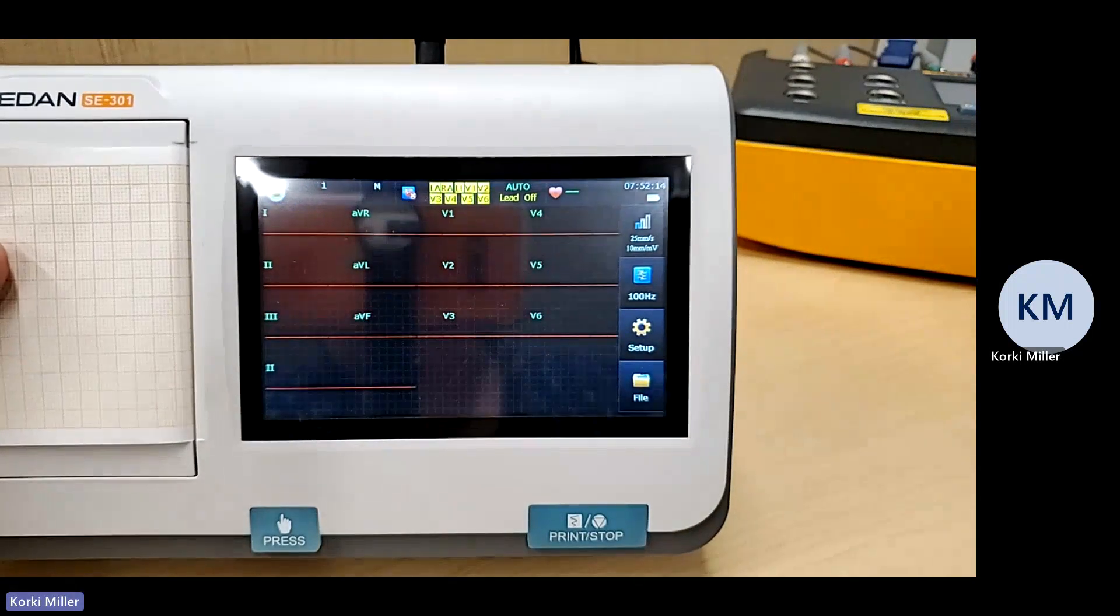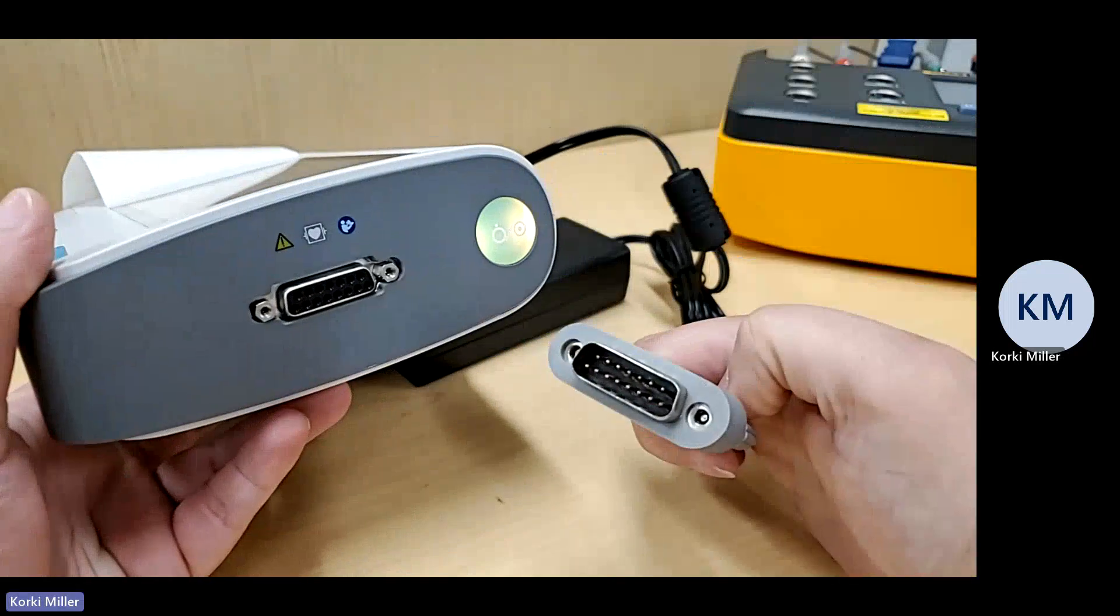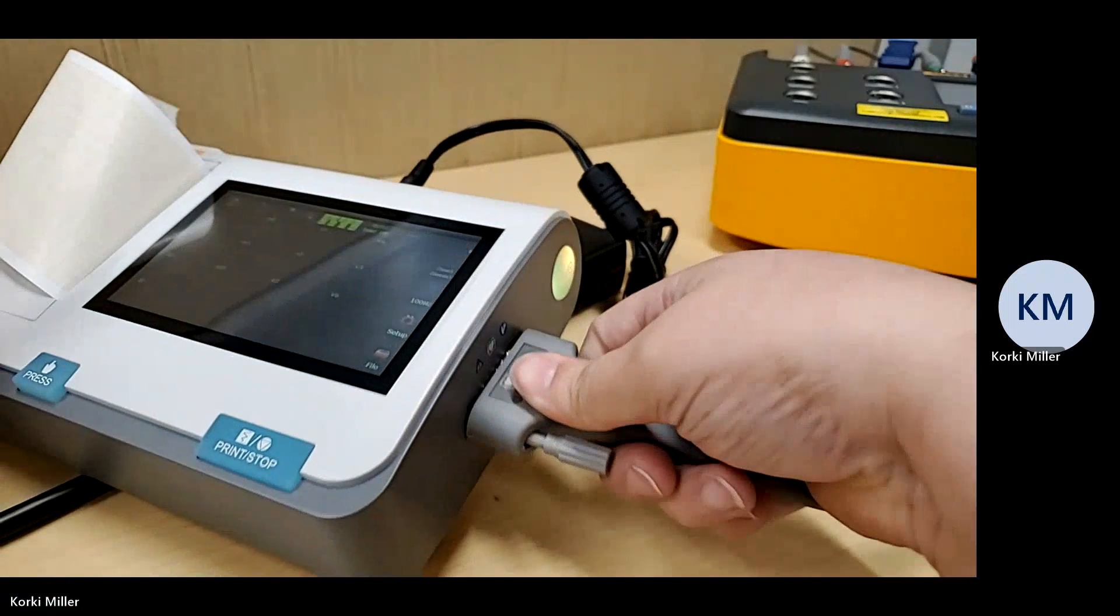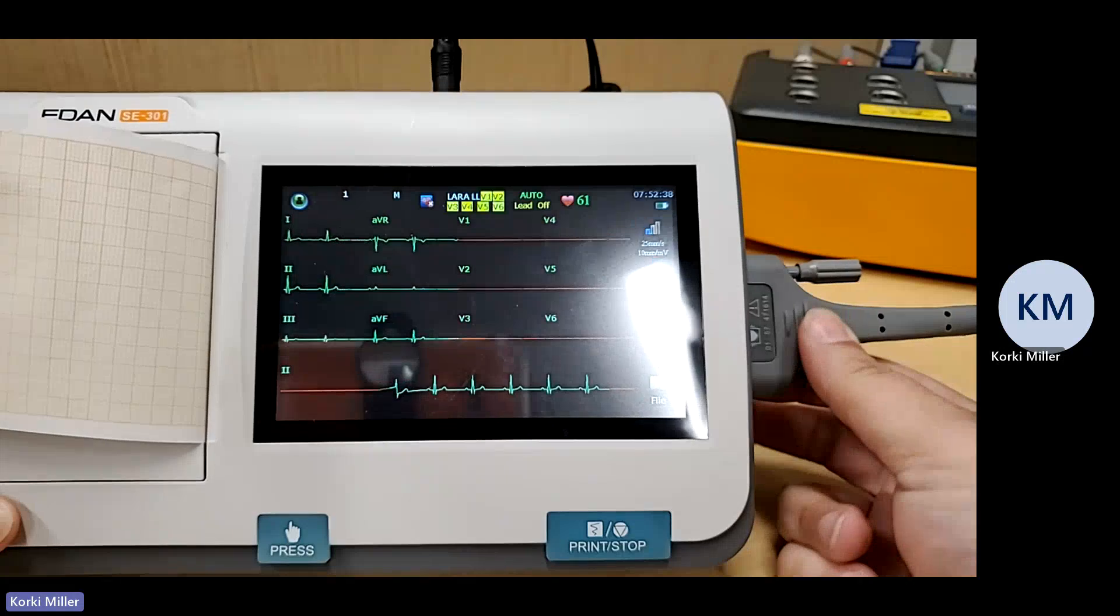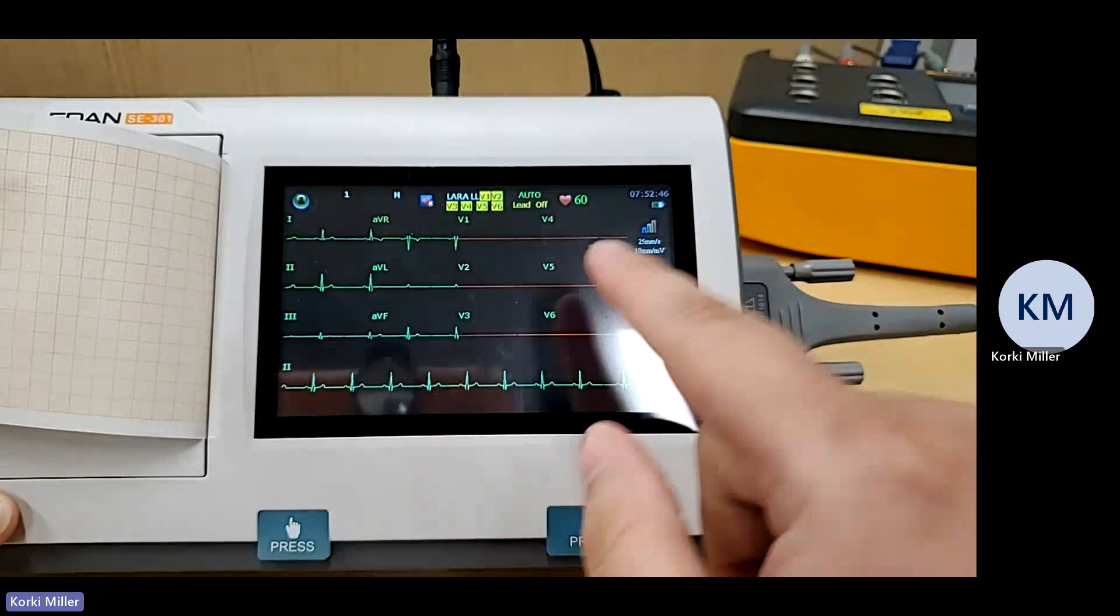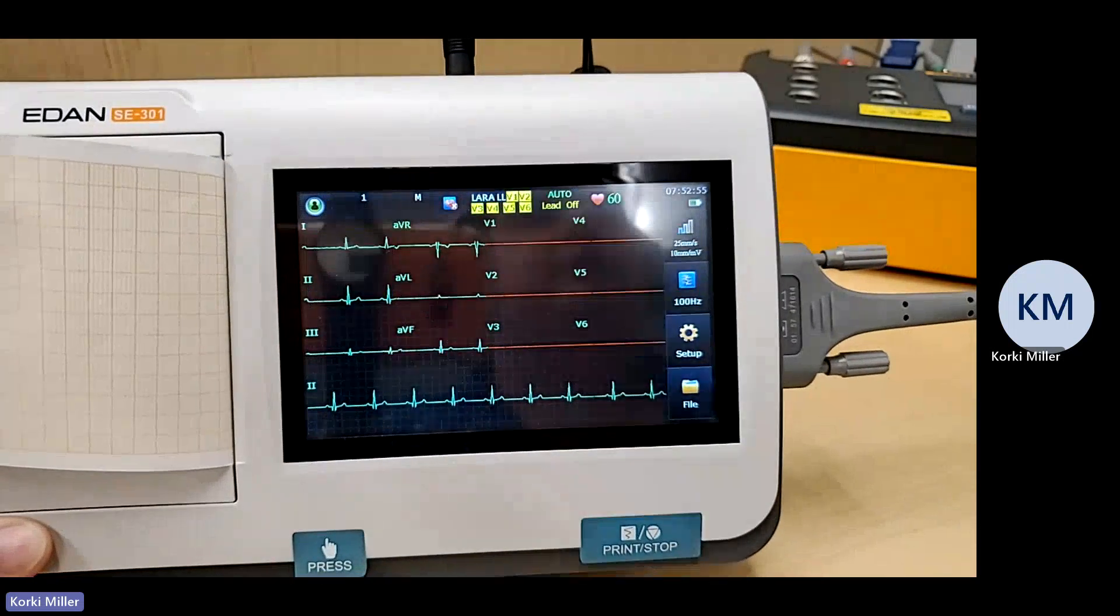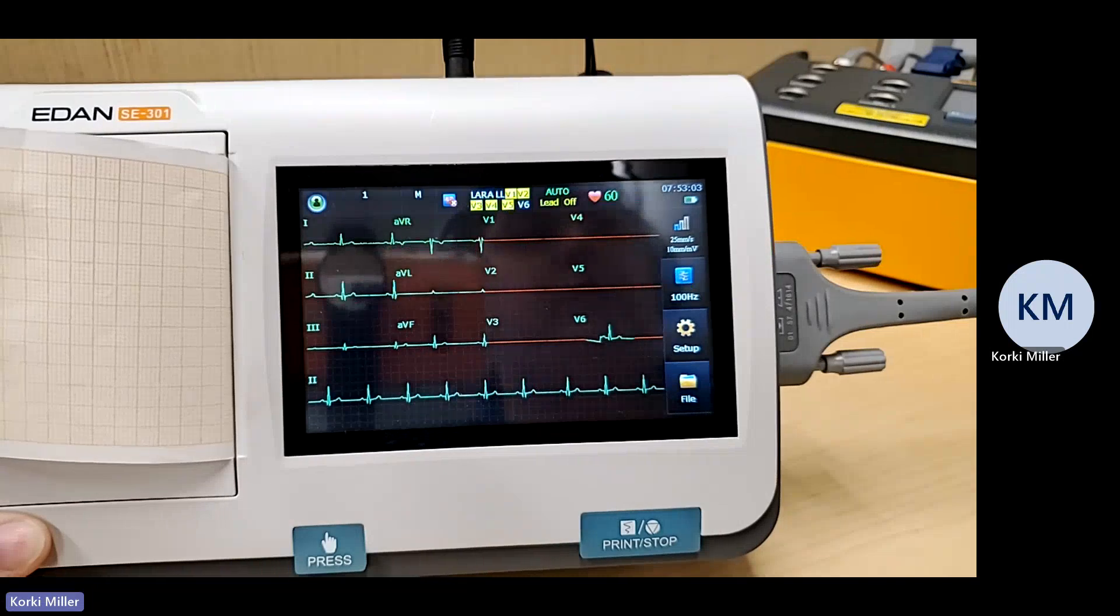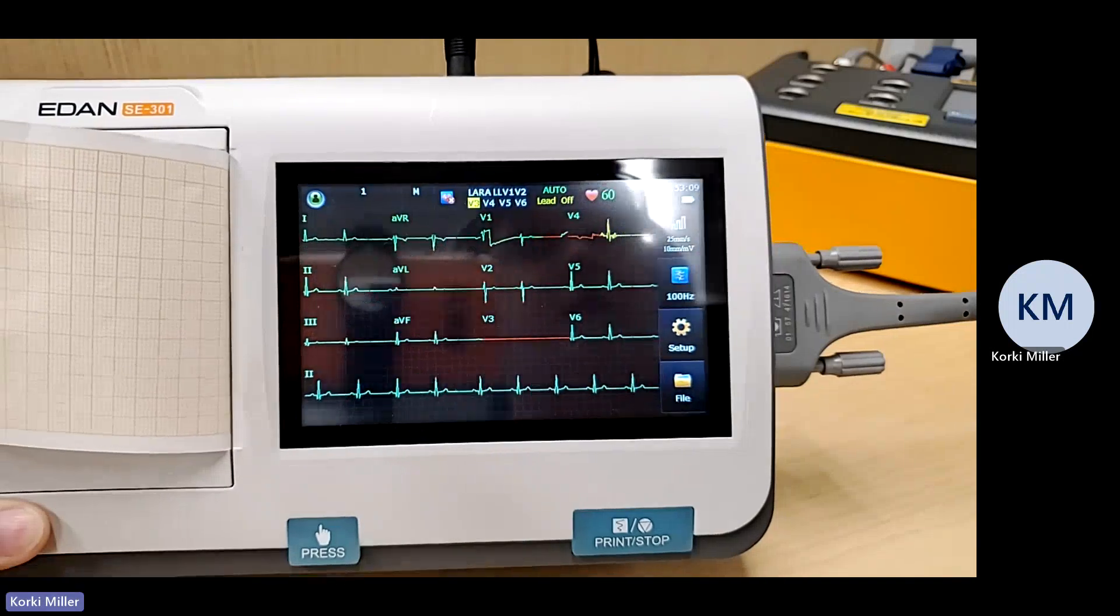We have a simulator set up for these demonstration purposes. Your connector and your unit only go in one way. So it's also designed for the small part to be at the top area. So you just plug that in here. And it's going to let us know if there's any adapters that we need to change. So it looks like our limb leads, which should be one, two, three. Those are okay, but we're having some difficulty on our V1 through V6. So while the other ones combine, the V1 through V6 are looking directly at those chests. So I'm just going to make sure that those are secure.